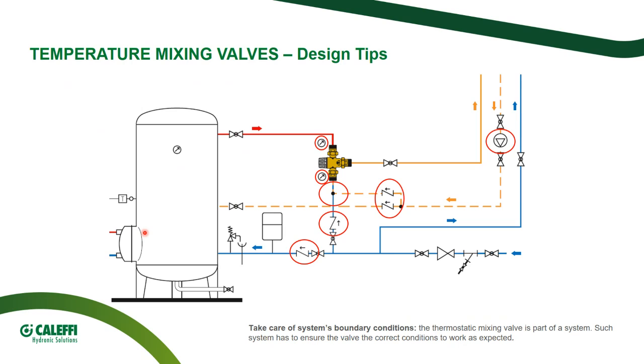Now, we saw the features of the devices in detail, but we have to remember that devices are part of a system. So during the design phase we also have to take account of the boundary conditions. There are other elements, even simpler, in the system that may affect the correct operation of the valve. If the thermostatic mixing valve or the electronic mixing valve is sized and selected correctly, but installed the wrong way, or if the system lacks some devices, for instance the check valves, there might be an influence on the normal operation.